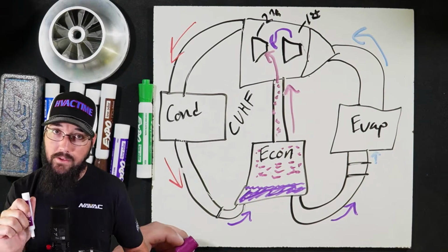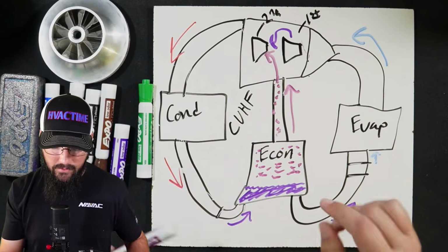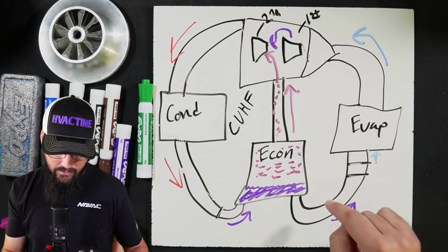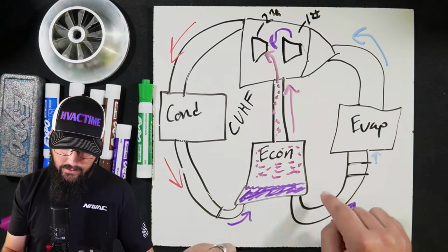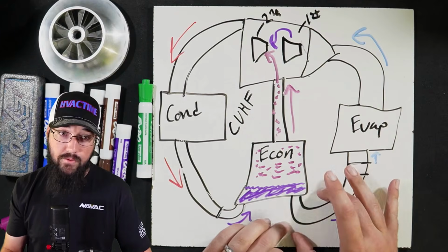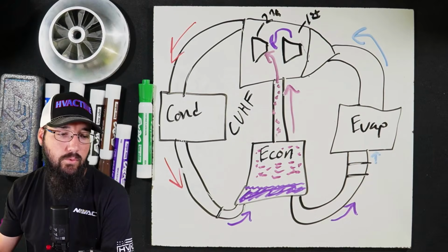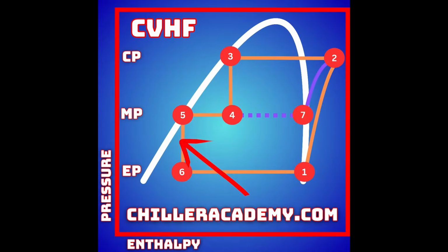Now, that's not the only thing being accomplished here. This is just one side of it. The other piece of this is in the liquid refrigerant that's left, and that's where we get into our enthalpy chart. So this is a basic saturation chart curve. There's nothing fancy going on here. What I've got is condenser pressure, my CP, my medium pressure, which is my MP, and my evaporator pressure, which is EP. That's what I'm establishing here.